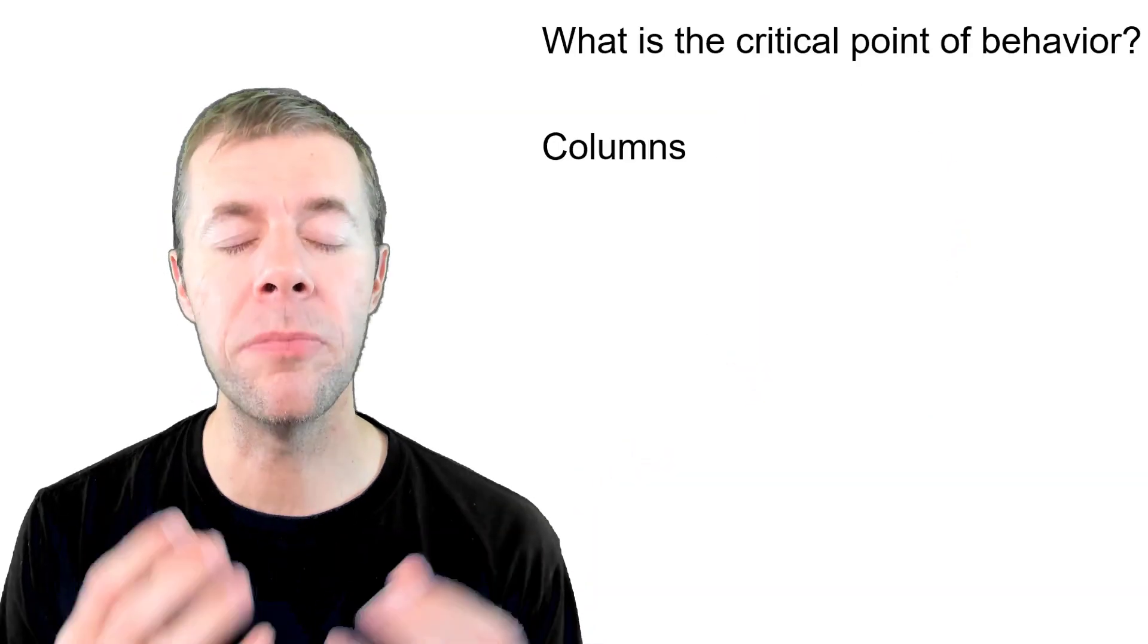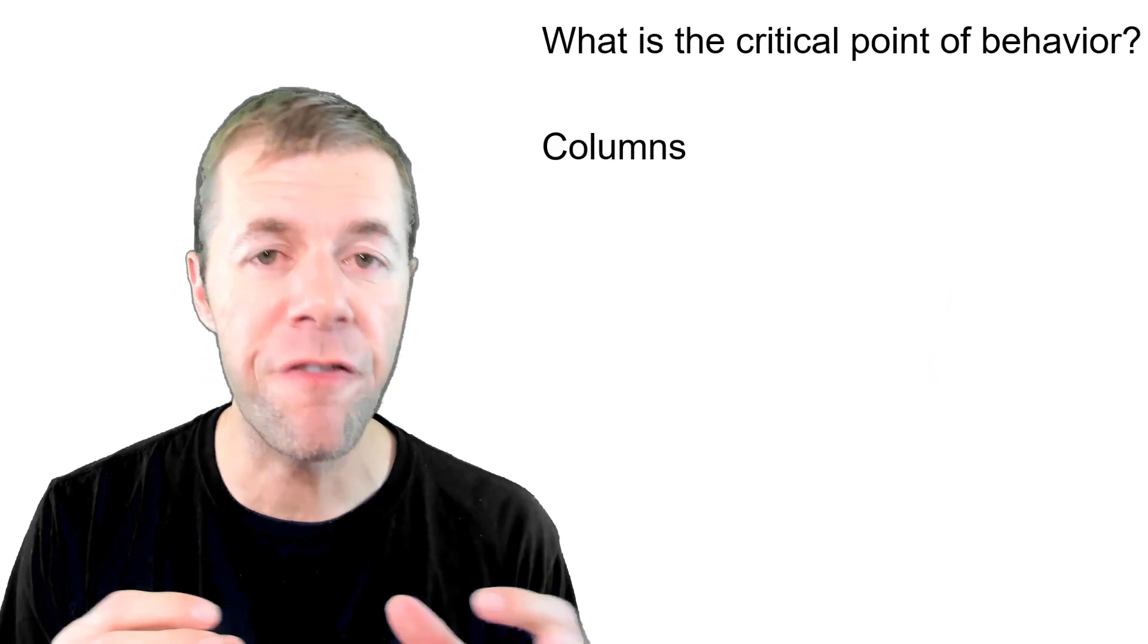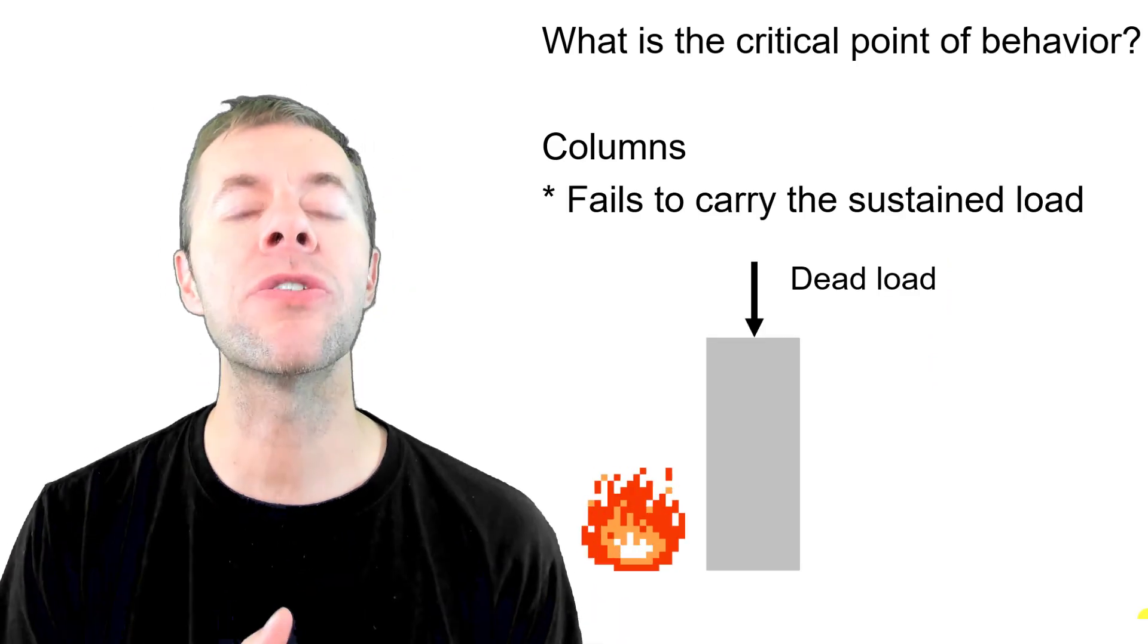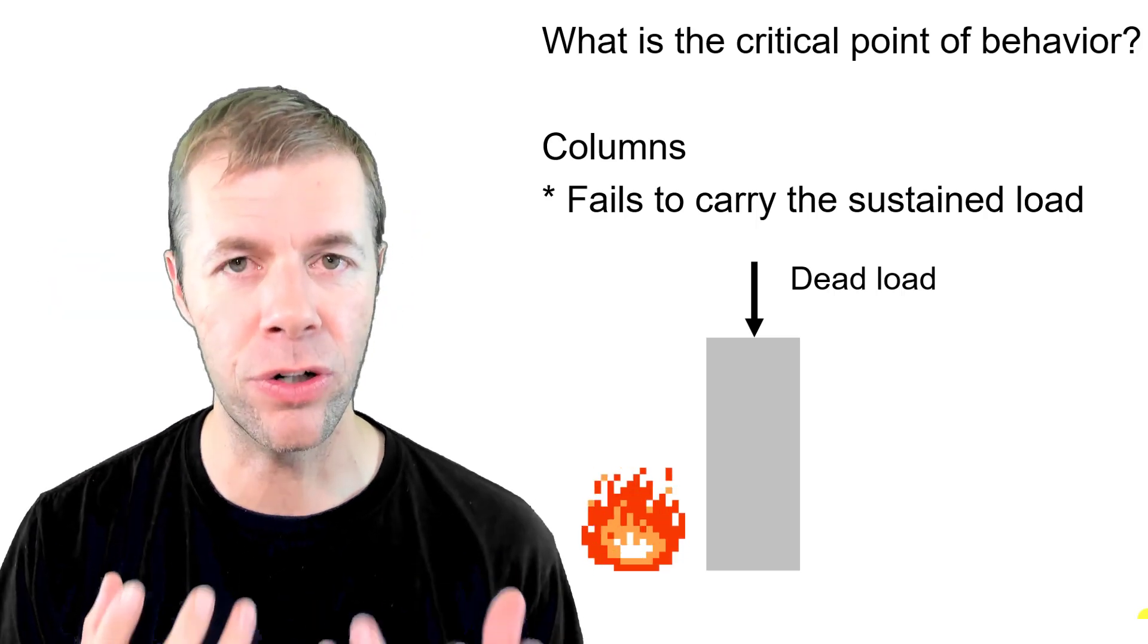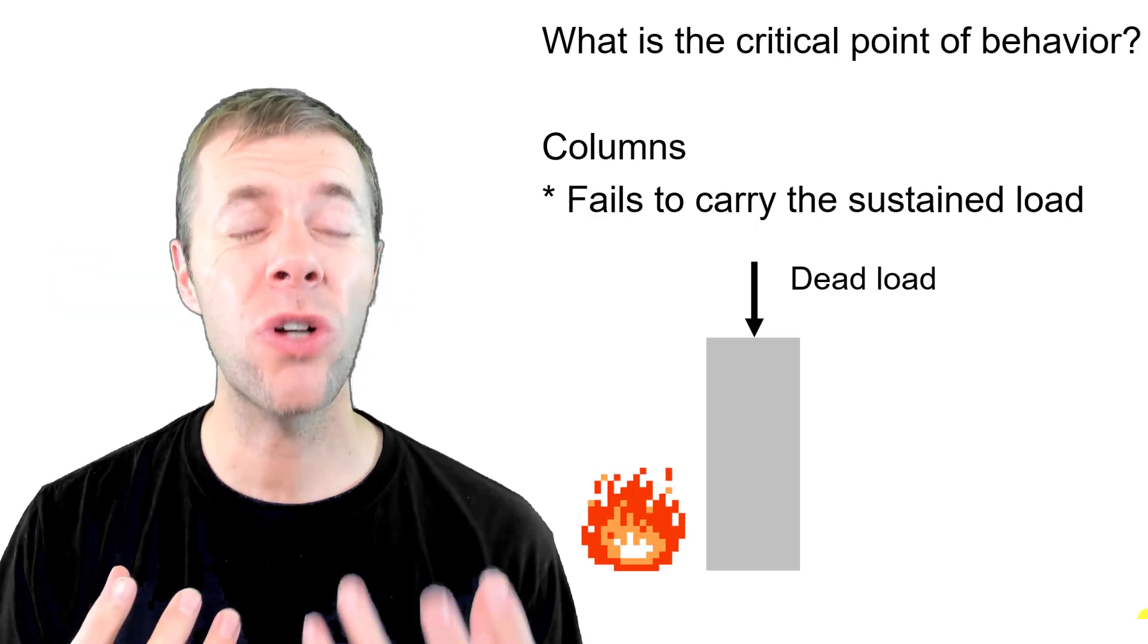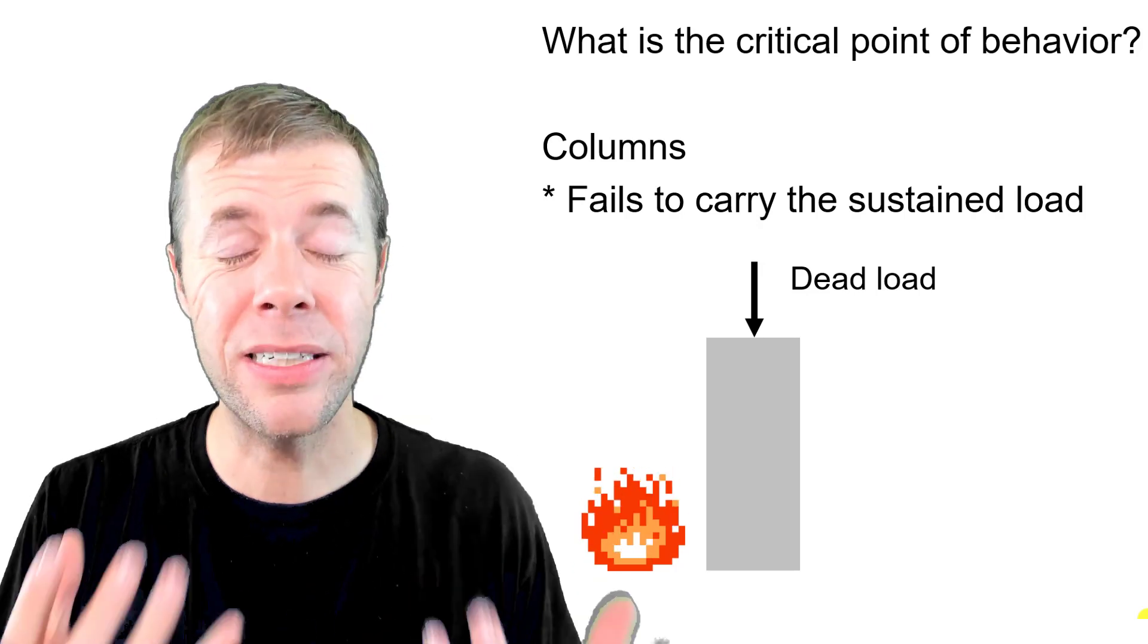For members like columns, they're a little bit different. You'll actually have fire all around it and it says how many hours does it take for it to hold the load in that standard fire temperature. As soon as the column starts to fail, that's when it's game over.